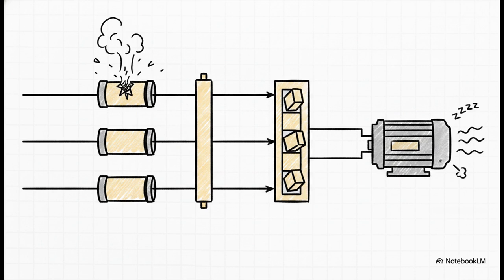The fuse holders are mechanically linked to an electrical release device. If just one single fuse pops, this release mechanism triggers, physically forcing the entire contactor to open automatically. This prevents a totally disastrous scenario called single phasing, where a motor keeps drawing power on only 2 phases, which would cause it to rapidly overheat and completely destroy its own windings.